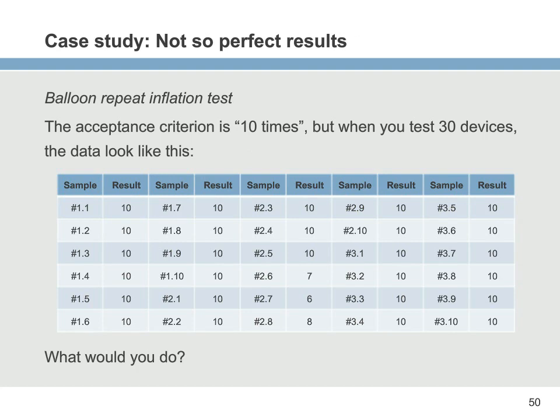I'm looking at slide 50. And this is a real case study, a balloon repeat inflation test. The acceptance criteria for this test was the balloon has to be inflated 10 times without bursting. Okay, so you test 3 lots, 10 each, so that's 30 total. And so there's your results. Okay, you got 10, 10, 10, 10, 10, 10, 10, 10, and then in lot 2, one of them went to 7 but burst at 8, one of them went to 6 and burst at 7, one of them went to 8 and burst at 9, and then the rest of them were fine as well.